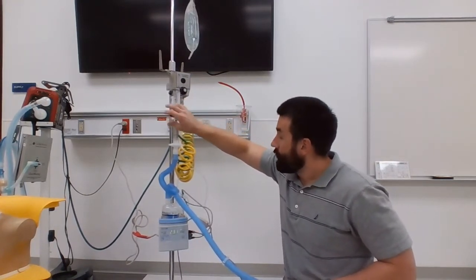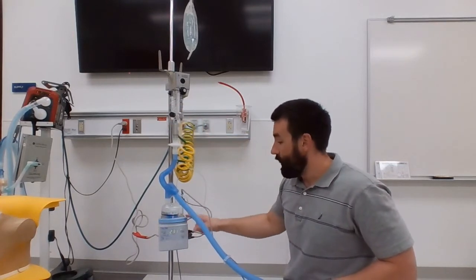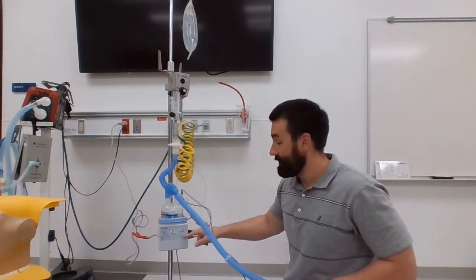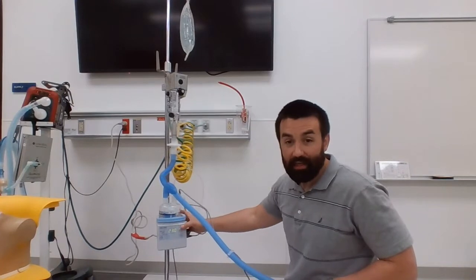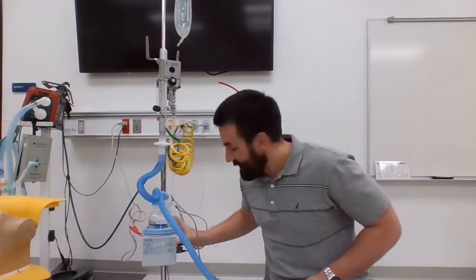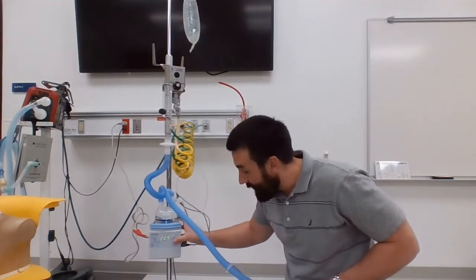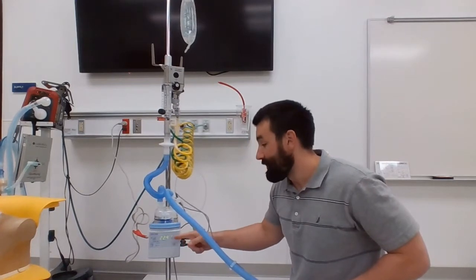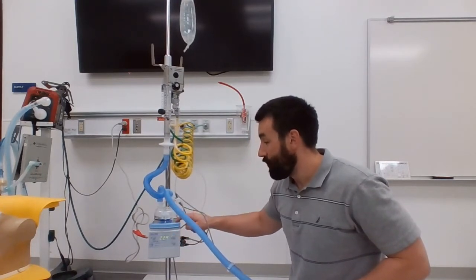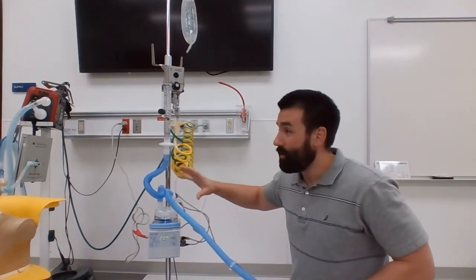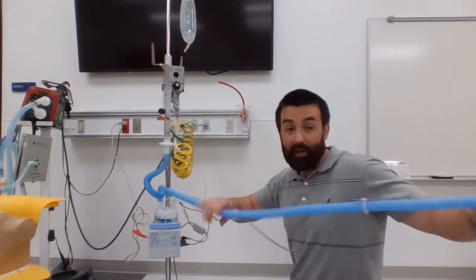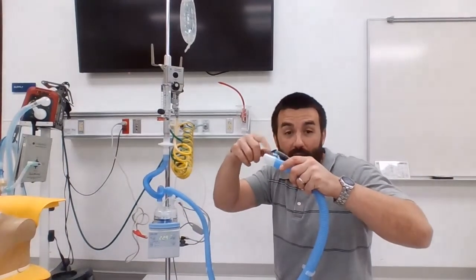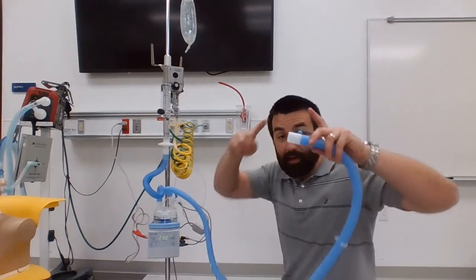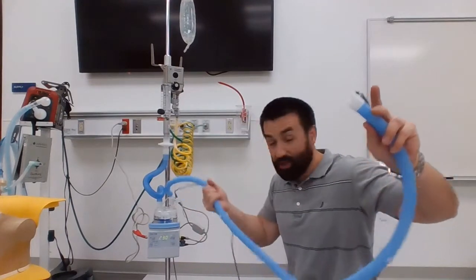As I start cranking flow through this thing, you'd see our measurements start adjusting. Because I'm on this invasive setting here, it starts out, it shows the invasive or non-invasive down low. It's going to realize the temperature is low. It's going to start heating this up a little bit more. That'll get that water hotter, and it's going to maintain a better temperature here. And then the ventilator will be making sure that the temperature between here and here stays the same by adjusting the electrical charge.